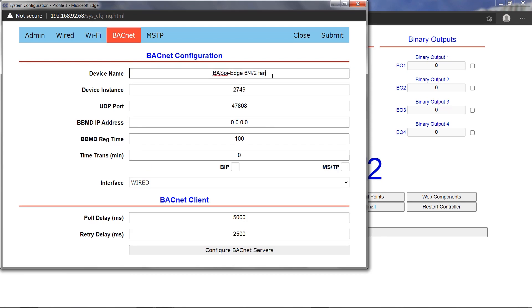The device name can be edited as desired to appear on the network. The device instance number must be set to a value which is unique throughout the entire BACnet network.